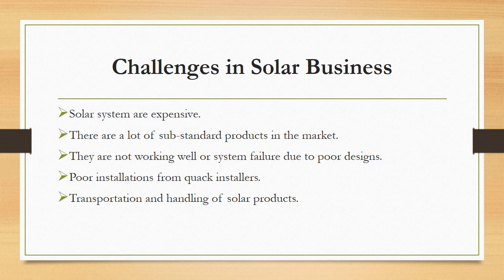Another issue is that by the time they calculated what was needed in the house, the client may not have had a television yet, or only had 2 fans. After installing the solar or inverter battery system, the client goes ahead and buys a television or other new appliances and connects them to the system, and the system starts failing. So the energy auditor needs to ask the client whether they plan to buy any appliances soon, so that can be factored in—so the system can carry everything and we won't have the issue of it failing or the battery not lasting.